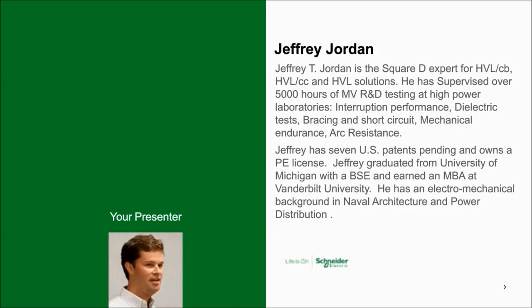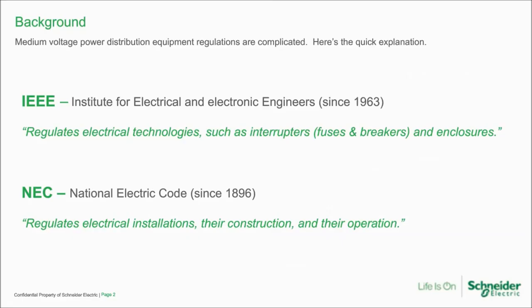It's best to start with a review of the IEEE and NEC codes. If you've ever looked for medium voltage in the NEC, you probably came up short looking for the chapter. There are a few references, but not like there are for low voltage. The ANSI standards for medium voltage are produced by IEEE and are intended to regulate the electrical technologies, whereas the NEC code regulates their installations as they relate to selective coordination. So we're going to focus primarily on IEEE today.